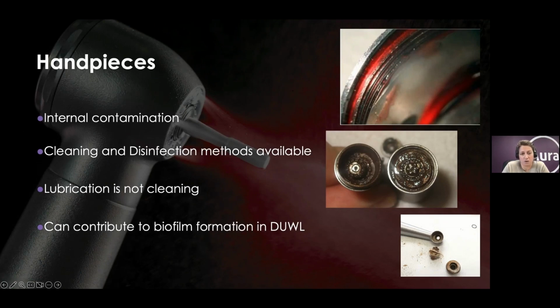Now, there are automated options and manual options for cleaning and disinfection, which sit to one side from oiling. Oiling on its own is not cleaning. Oil is going to lubricate the internal surfaces, but is not going to clean or disinfect them. You can use automated processes, such as putting handpieces in washer disinfectors, if they are validated for that. You can use semi-automated methods where you have machines. Lots of the handpiece manufacturers have these, where they do a cleaning process and then also oil them. Or there are manual processes where you can spray cleaning and disinfection chemistries through, and then oil them at the end.